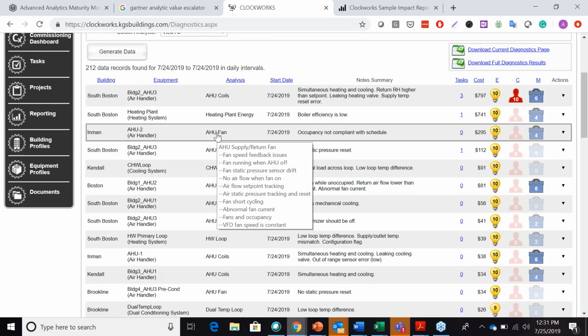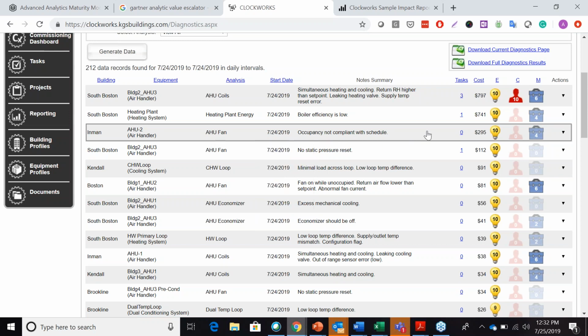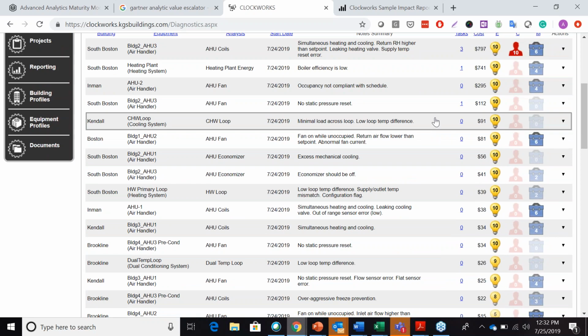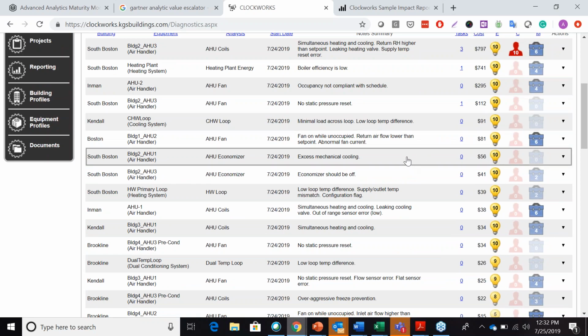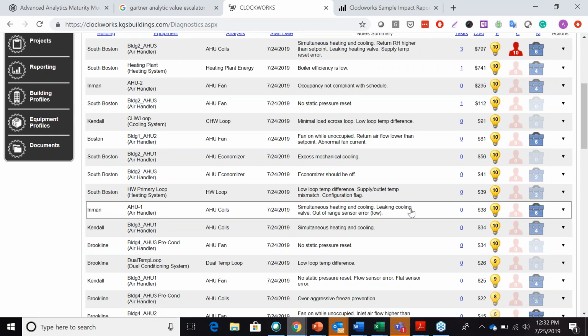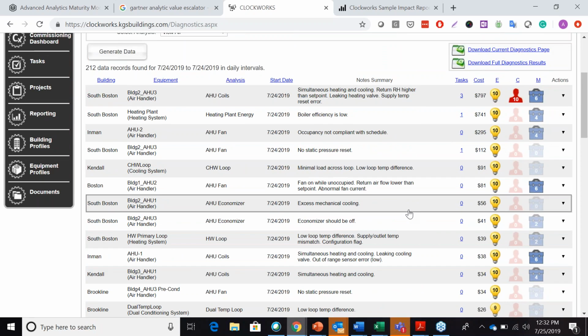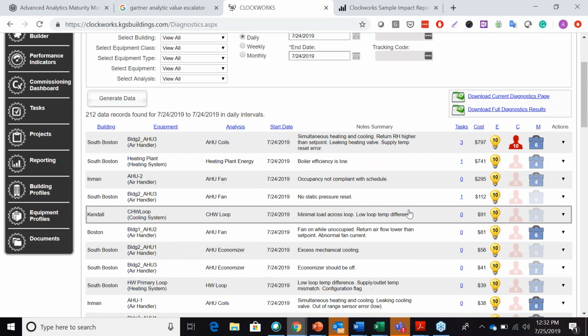So on this one here, AHU fan is a large block of sophisticated diagnostic code that looks to say, are there any fan speed feedback issues? Or are there any times where there's no airflow, where the fan's on, or where there's sensor drift occurring, or abnormal fan currents, or short cycling, or you name it? What's been found here is that occupancy is actually not compliant with the desired schedule. Or that there's a minimal load across the chilled water loop, excess mechanical cooling when we could be using outdoor air, and down the list. So these are sort of common, typical top examples related to energy to be able to pinpoint what's really going on here. Now, if we click into one of these, we get a full report.